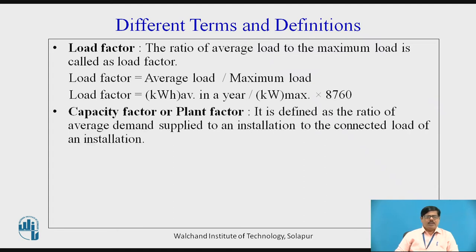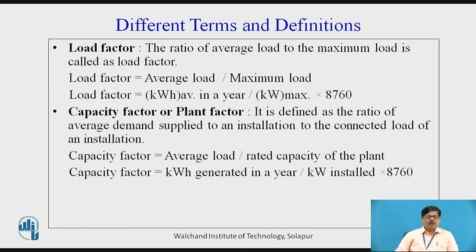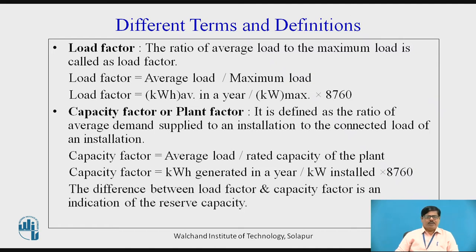Another important factor is the capacity factor, or plant factor. It is defined as the ratio of average demand supplied to an installation to the rated capacity of the plant — that is, average load divided by rated capacity. For an annual basis, the capacity factor equals the number of kilowatt-hours of electrical energy generated in a year divided by the kilowatt installed multiplied by 8760 hours. The difference between the load factor and the capacity factor is an indication of the reserve capacity.